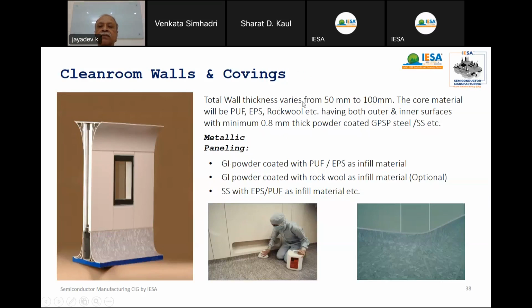Here, the total thickness of the wall panel, the puff panel, I'm basically explaining the puff panel, varies from 50 mm to 100 mm thick, depending upon different sizes. The core material used inside this will be puff material or EPS or rock wool. And it has outer and inner surfaces with 0.5 mm thick powder coating. GPSP means galvanized plain single pass steel, which you have to use. Properly select the steel before fabricating wall panels. It may be SS also. So the three types of materials you can use are powder coated GI with EPS, powder coated GI with rock wool as infill material in some optional cases, and stainless steel with EPS or rock wool infill material, depending upon the need.